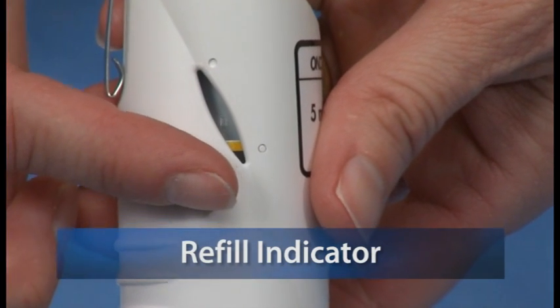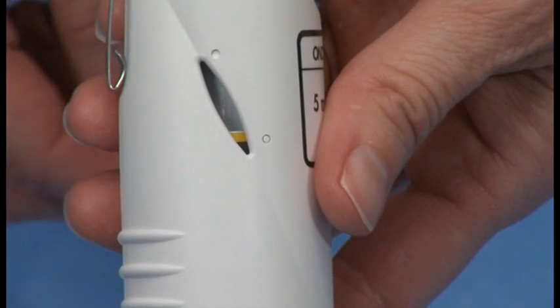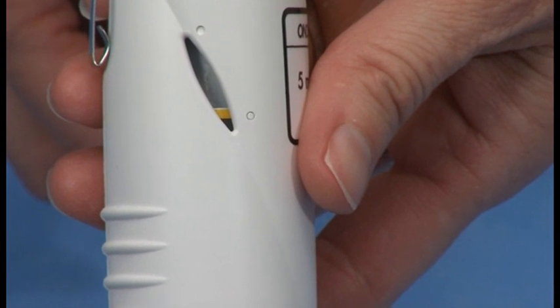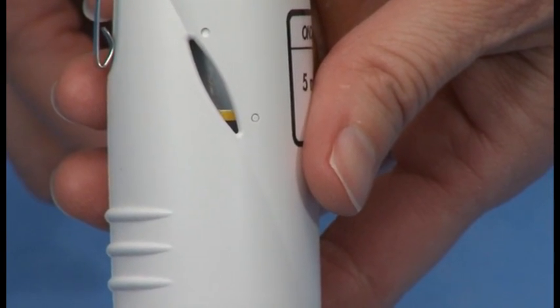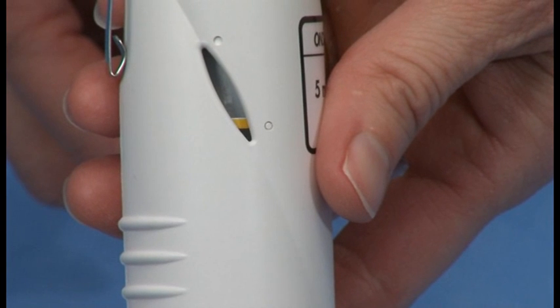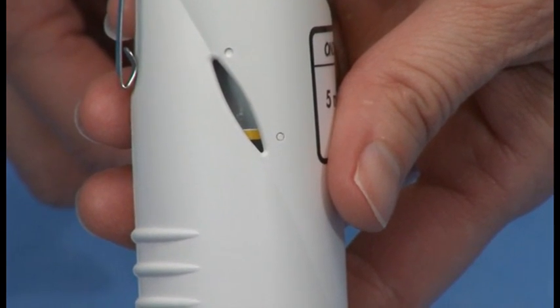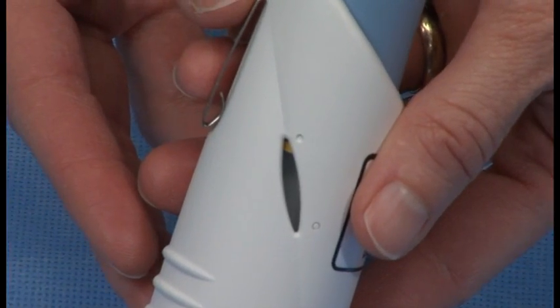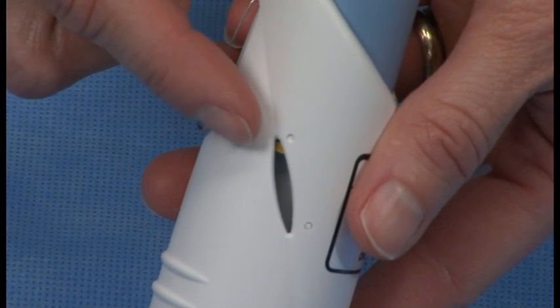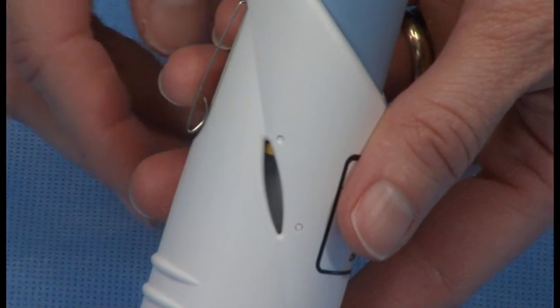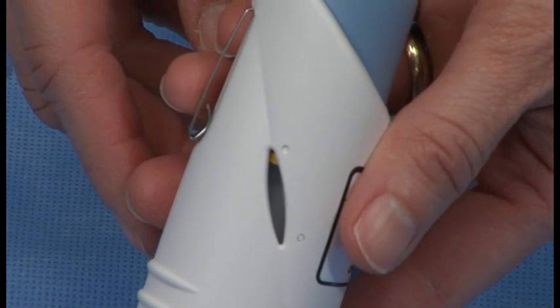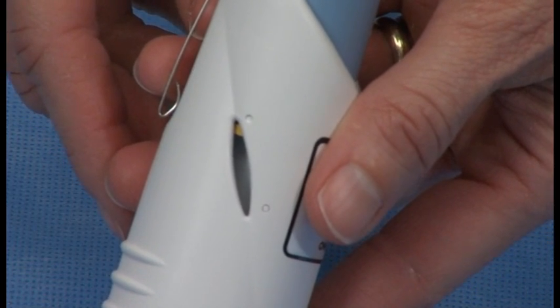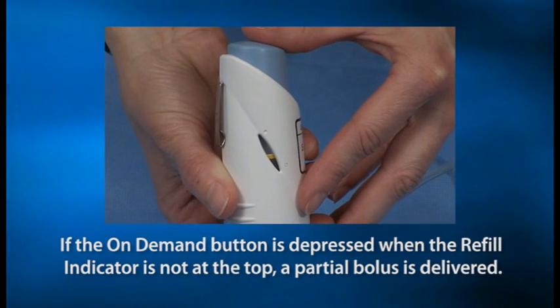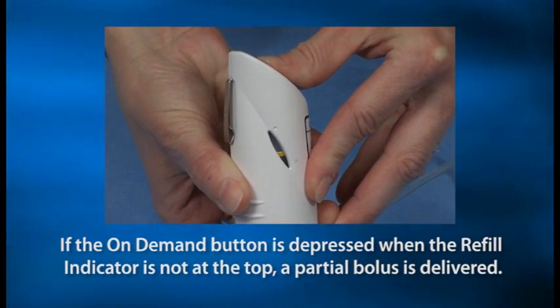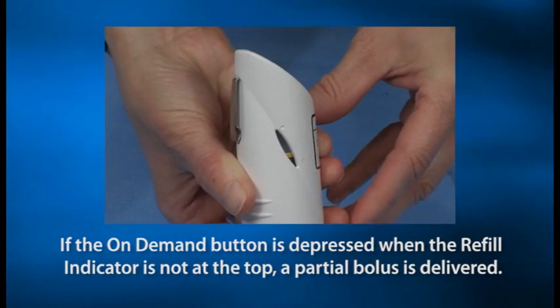The refill indicator, which is a yellowish line located in the clear window on the side of the on-demand canister, will be at different levels depending on how full or empty the canister is. After delivering a bolus, the line will be at the bottom indicating that a bolus has just been delivered. After approximately 1 hour, the canister should be refilled and the line will then be at the top. The bolus is then ready to be used again if needed. If the on-demand button is depressed when the refill indicator is not at the top, only a partial bolus will be delivered.